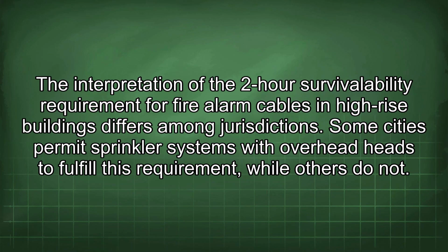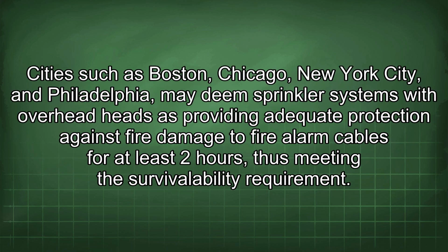The interpretation of the 2-hour survivability requirement for fire alarm cables in high-rise buildings differs among jurisdictions. Some cities permit sprinkler systems with overhead heads to fulfill this requirement, while others do not. Cities such as Boston, Chicago, New York City, and Philadelphia may deem sprinkler systems with overhead heads as providing adequate protection against fire damage to fire alarm cables for at least 2 hours, thus meeting the survivability requirement.